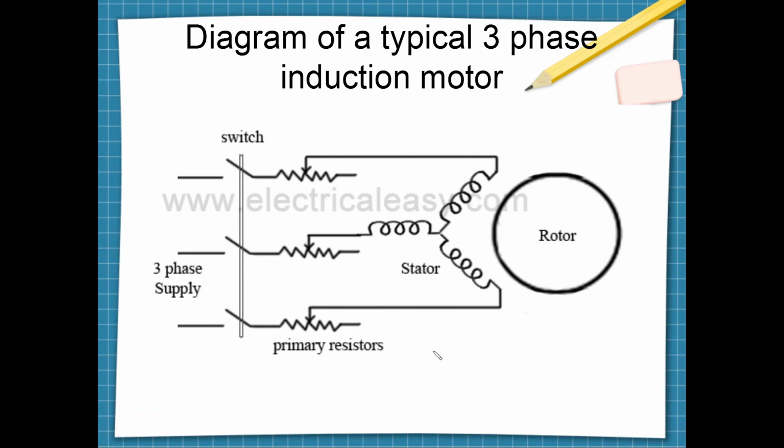In starting we need star connection because the motor cannot handle a large current, so we use star connection to reduce the current and voltage, and when it starts rotating then we can apply delta connection supply. That is why we need star delta starters in submersibles.